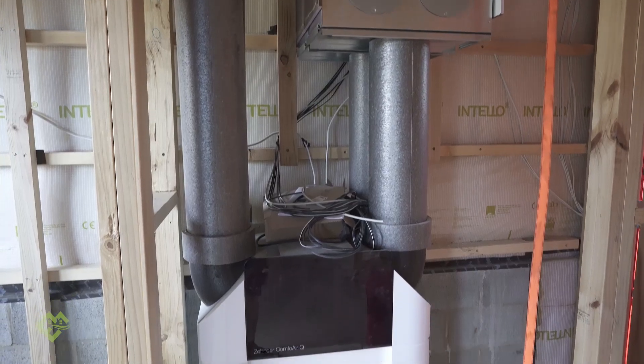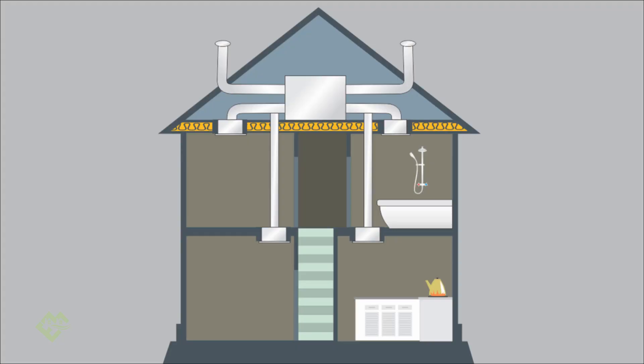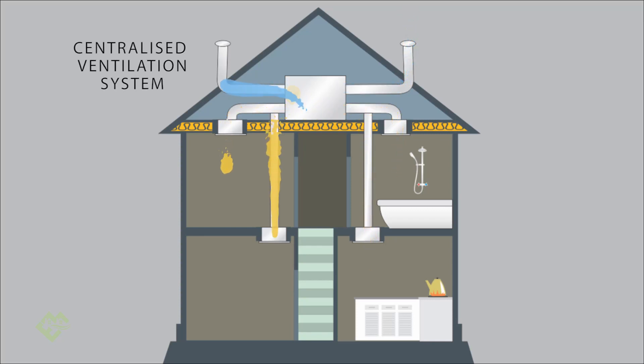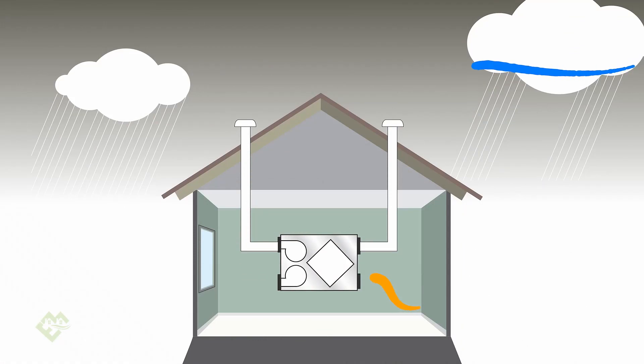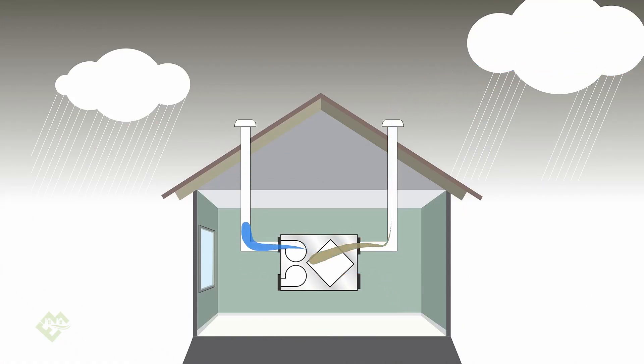The ultimate solution is a constant 24-hour ventilation system. However, if you simply have a mechanical fan constantly pumping outside air into your house, you lose a lot of energy — you need to condition much more outdoor air with heating or cooling throughout the year. That's why the newer, more sustainable trend is to use an energy recovery unit or heat recovery unit, which exhausts stale air and brings in fresh air simultaneously through the unit itself. This allows heat and energy to transfer from the exhaust to the incoming air — a process called pre-conditioning — tempering the incoming air to match indoor conditions more closely.